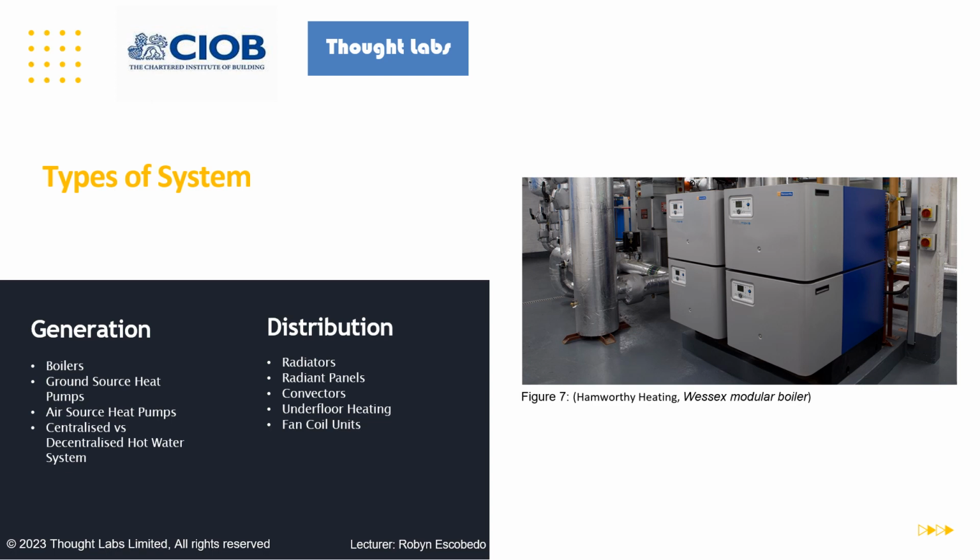Because boilers can be modularised, at times of low output, e.g. 60 kilowatts, if each of these boilers was 100 kilowatts, then only one of those boilers would be running. This would save 300 kilowatts.